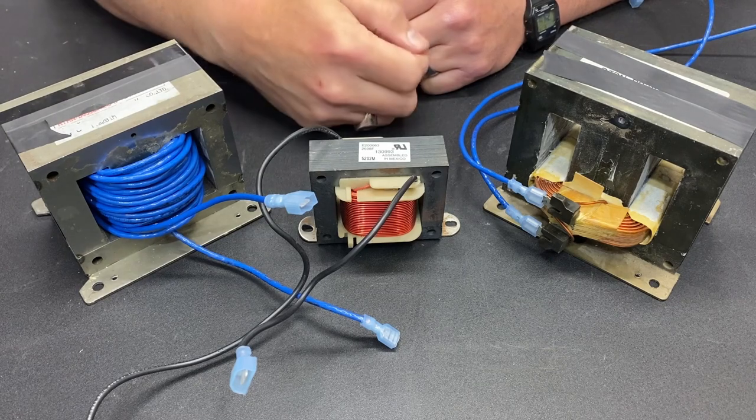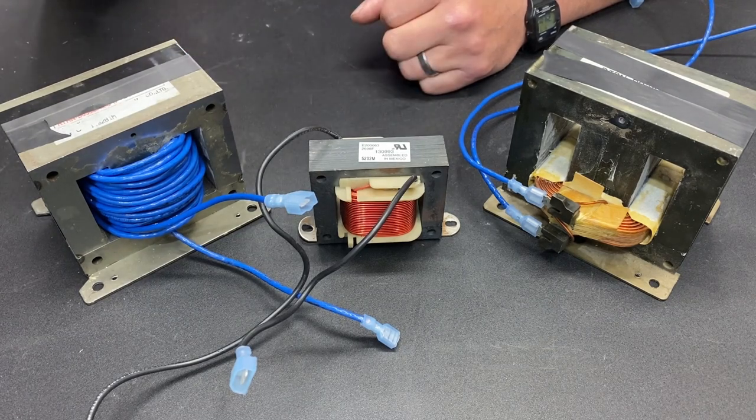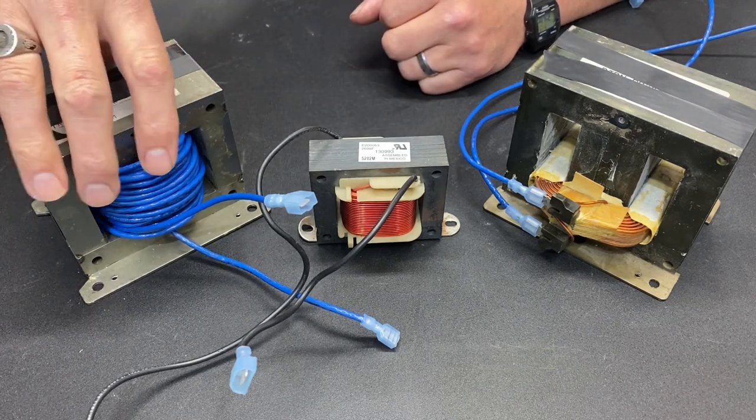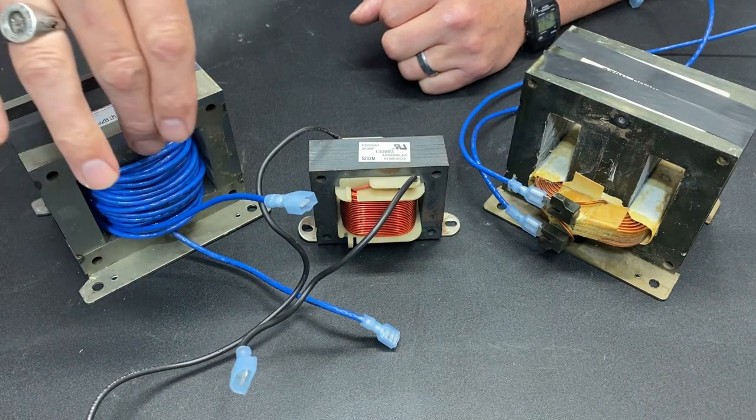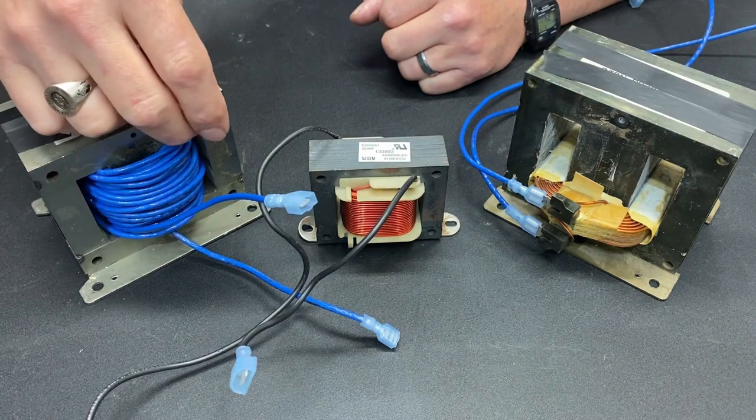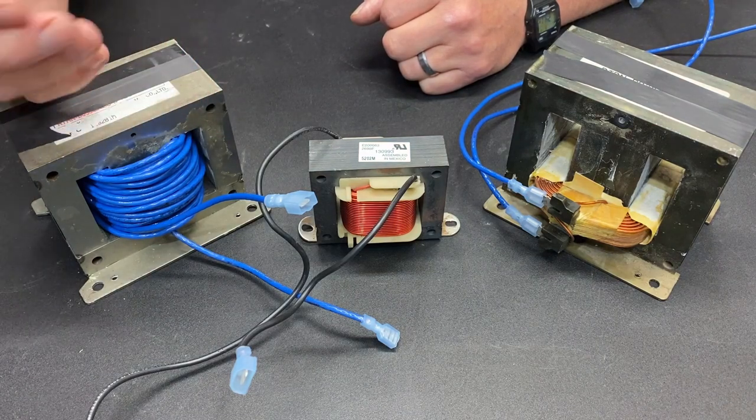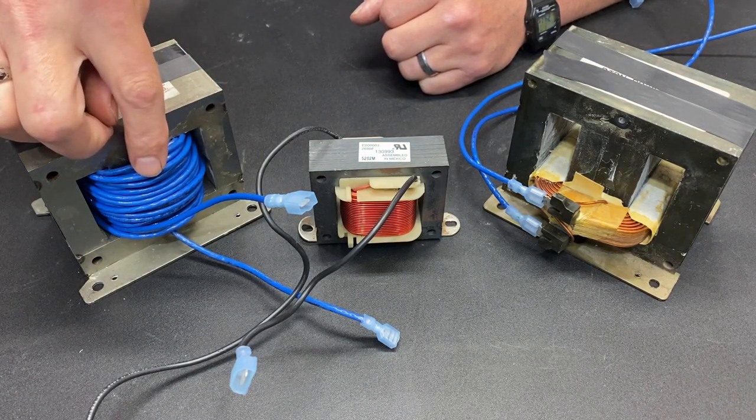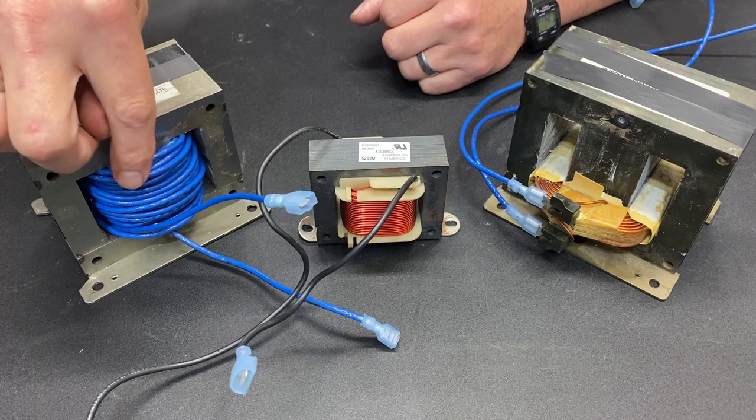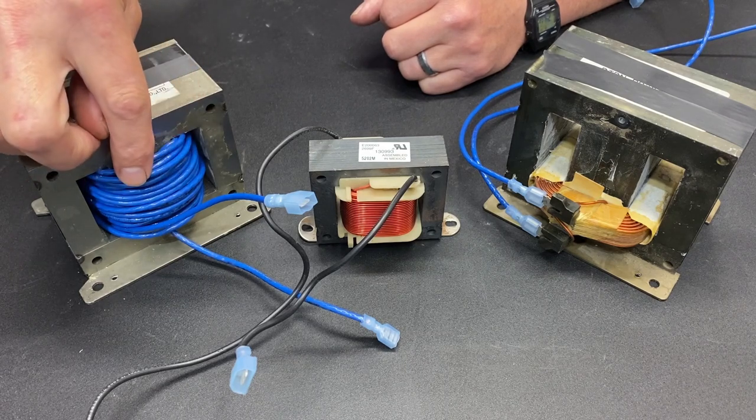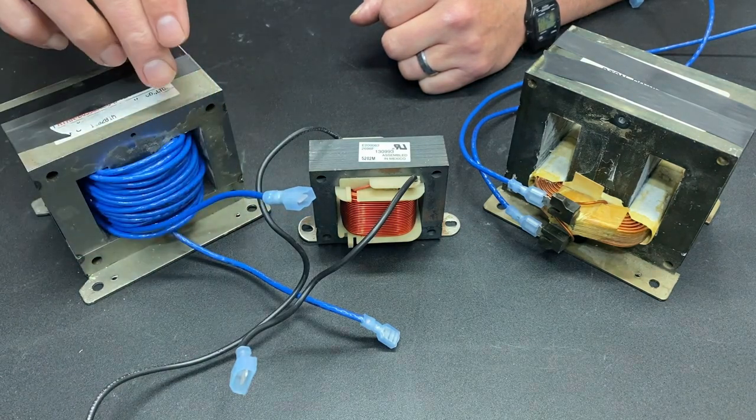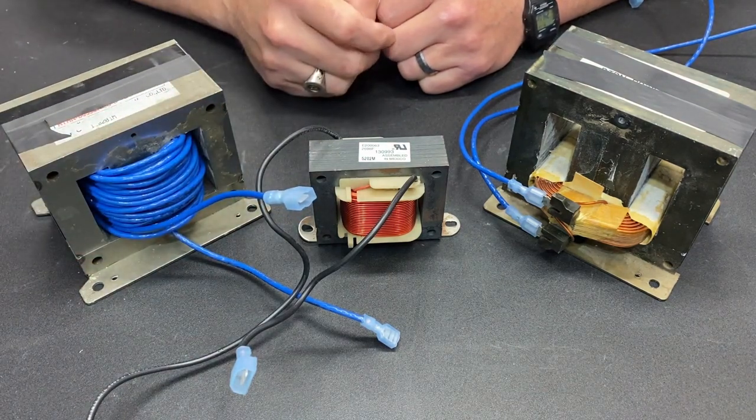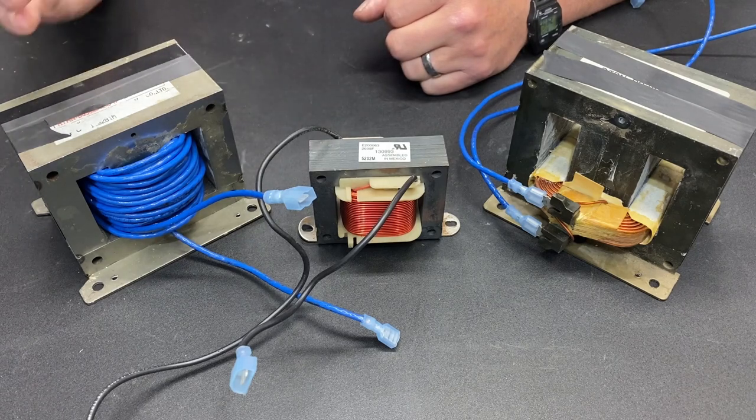Now, a little extra noise in the shop, no big deal. But my concern is that humming is coming from vibrations. So these wires are vibrating. That means the wires are going to be rubbing against this metal body. And there is a good chance that that vibration is going to cause you to wear through the insulation on the wires and ultimately result in a direct short between the wire and the body of the transformer. And at that point, we run the risk of burning things up.